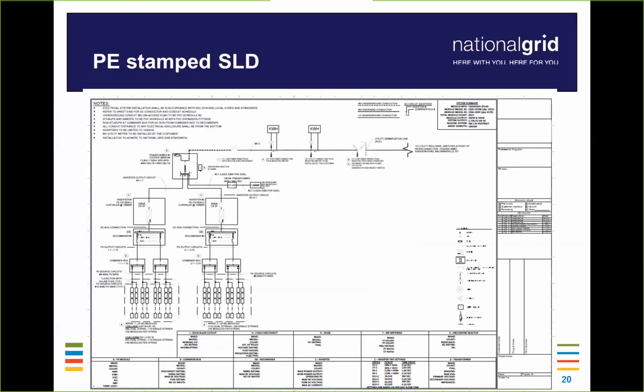On this drawing, they identify the point of common coupling. We would be interested in that. And then as you follow the electrical circuit down into the premise system, any transformers that are required to convert voltages up or down to a utilization for the site equipment that's required for operation would be something we'd be interested in. If there is a ground bank or a neutral reactor, that would be required to be shown. As well as the general arrangement electrically of the inverters, and whether that transfers down to collector panels or whatever the distribution arrangement makeup is down to the panels.